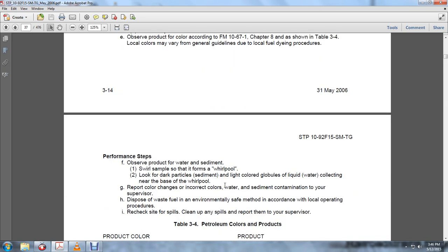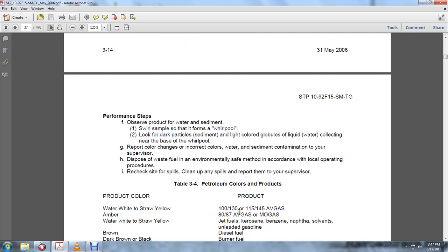Performance steps: observe products for water and sediment. Swirl the sample so it forms a whirlpool. Look for dark particle sediments and light colored globules of liquid water collecting near the base of the whirl. Report any color change, incorrect colors, water, sediment, or contamination to the supervisor. Dispose of the waste fuel in an environmentally safe method in accordance with the local operating procedures. Recheck the site for spills. Clean up any spill and report it to the supervisor.